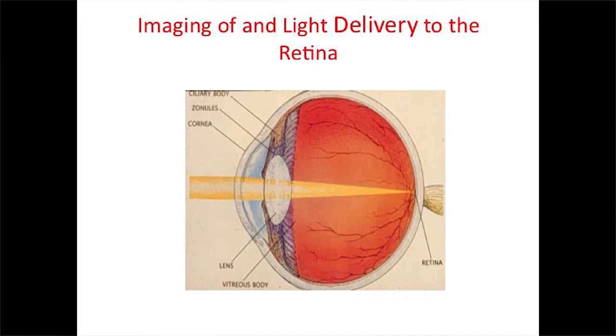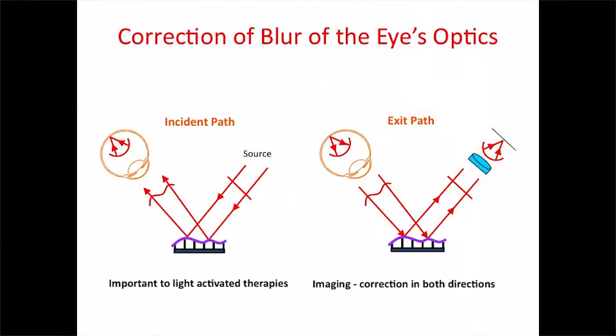When we image, in our case we're using the cornea and the crystalline lens as our objective, focusing the light at the back of the eye, and you can see the various vessels and other structures at the rear of the eye that we're most interested in. Because of the imperfections in the optics of the eye, we have to use adaptive optics — deformable mirrors that we deform by fractions of microns to correct the aberrations and optical imperfections of the eye to create a very high resolution image.